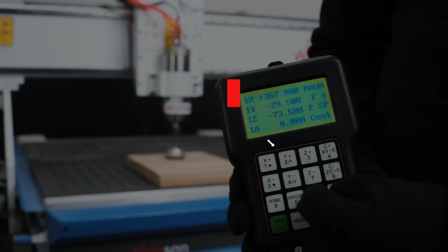We need to switch to the slow mode and start lowering the instrument to material until we reach point 0. Then examine whether there is touching or not. If there is none, we need to perform steps of 0.1 mm until the instrument reaches the workpiece and starts scratching it a little. We found that we needed to add another 0.4 mm.